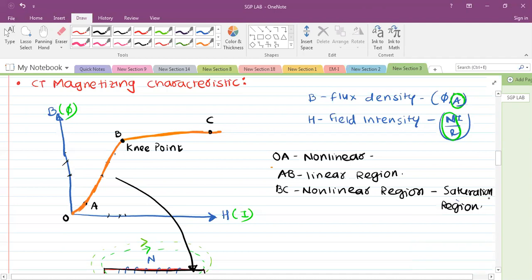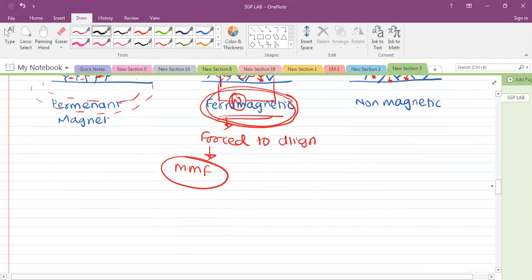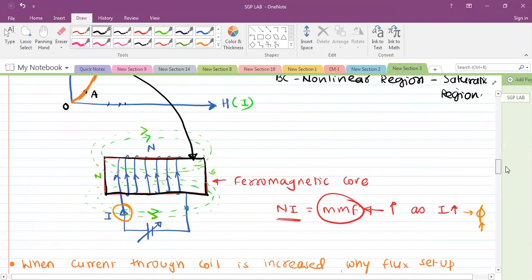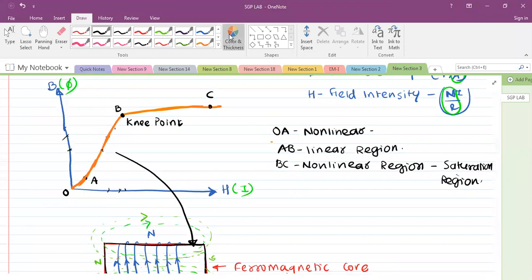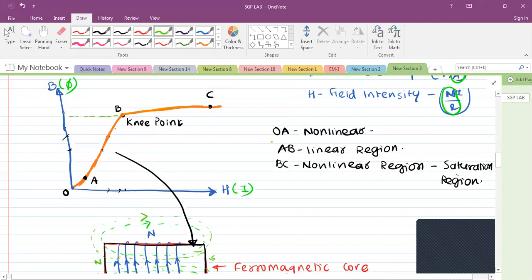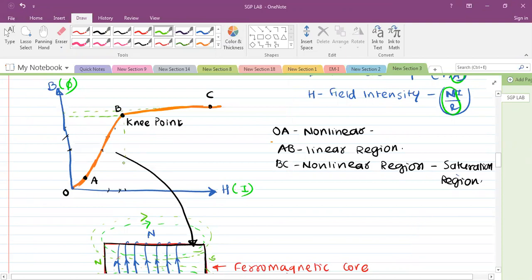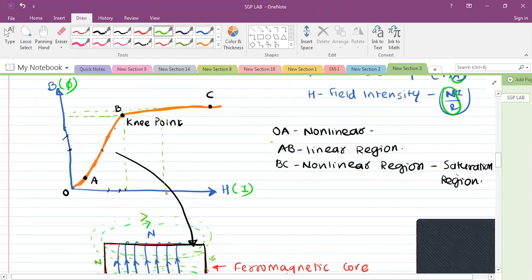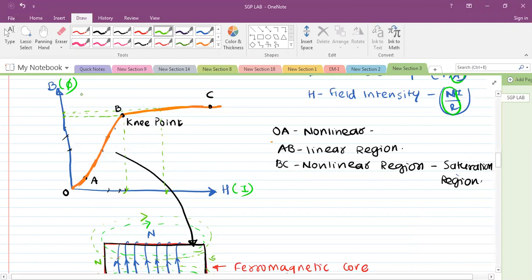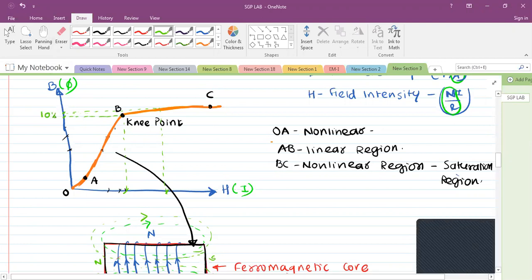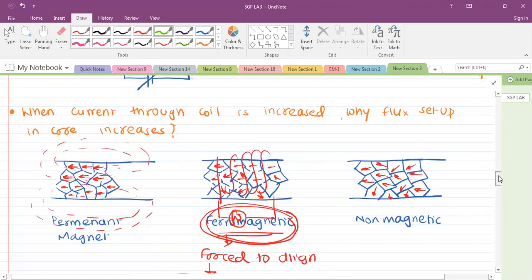Now understand what will happen. What is the knee point? Let me define it. Knee point voltage, generally called KPV, is a point on the saturation characteristic beyond which, if you require only 10% change in the flux, it requires 50% change in the current. That is what is called the knee point voltage.